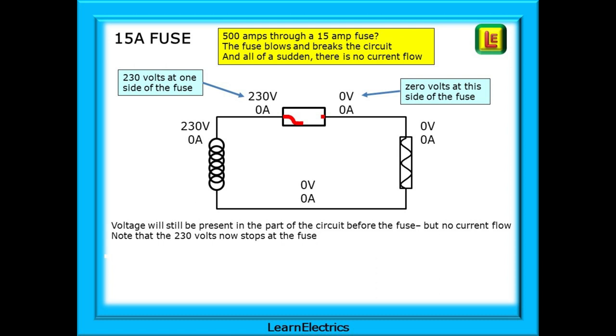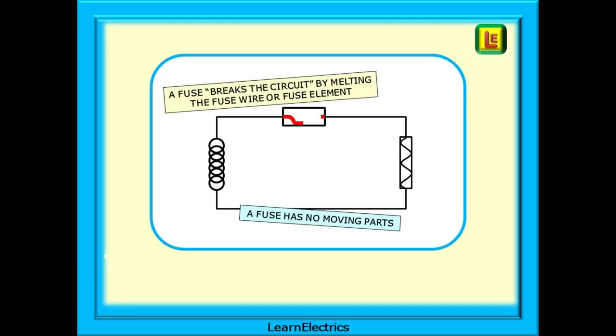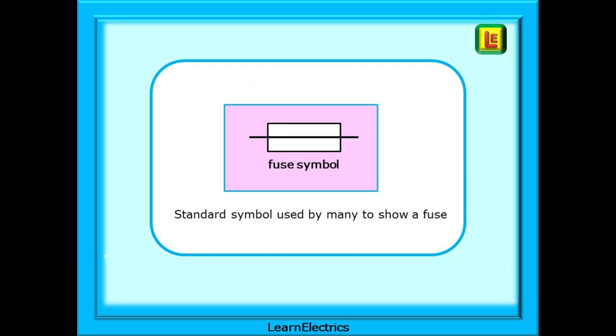Look at the voltages that are present now that the fuse has blown. There will be 230 volts present on one side of the fuse and zero volts on the other side. Be aware of this — just because the fuse is blown and the circuit is dead does not mean that all of the circuit is dead. There will still be 230 volts at certain points. When it comes to fuses, remember that a fuse breaks the circuit by melting the fuse wire or fuse element, and a fuse has no moving parts. This is the symbol for a fuse, with the line through the center indicating the fuse wire or fusible link.